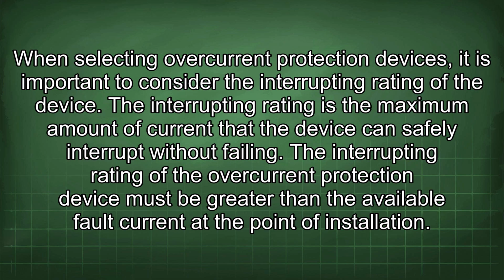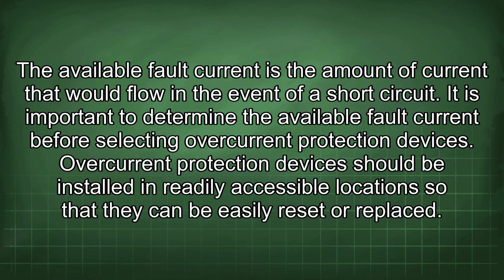When selecting overcurrent protection devices, it is important to consider the interrupting rating of the device. The interrupting rating is the maximum amount of current that the device can safely interrupt without failing. The interrupting rating of the overcurrent protection device must be greater than the available fault current at the point of installation. The available fault current is the amount of current that would flow in the event of a short circuit. It is important to determine the available fault current before selecting overcurrent protection devices.